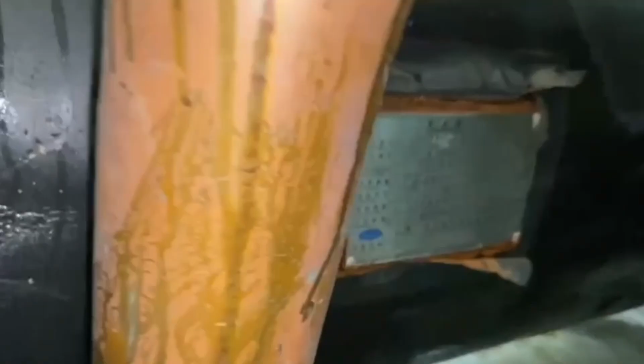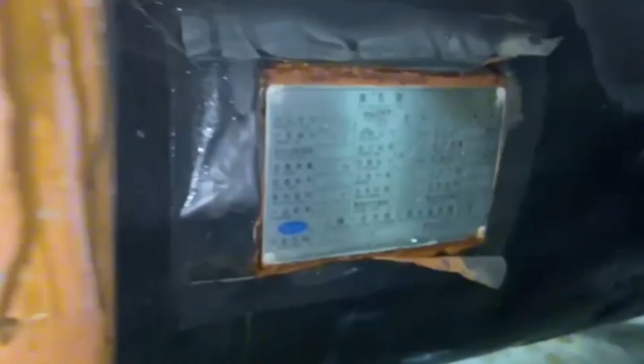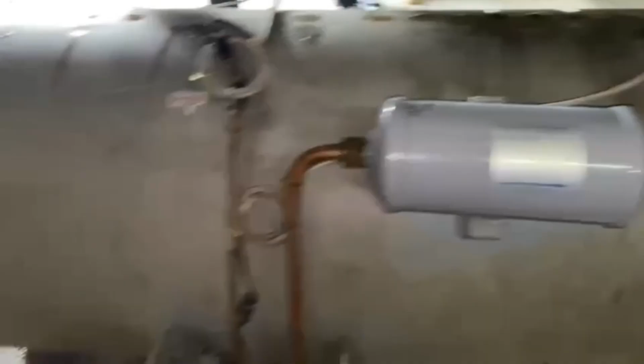The evaporator functions to cool down warm water from the building before sending it back as chilled water. The condenser removes heat from the refrigerant using cool water from the cooling tower. The entire process is controlled by the electric chiller, which uses electric energy to keep the cooling cycle running efficiently.